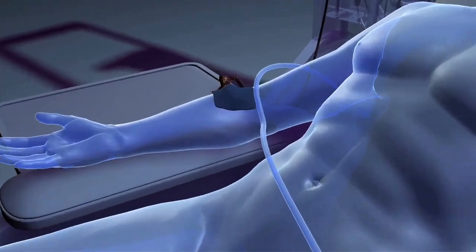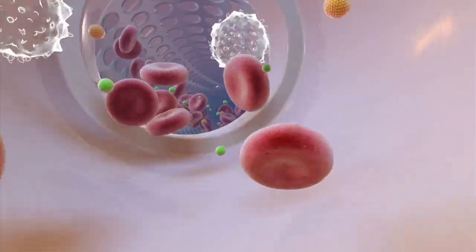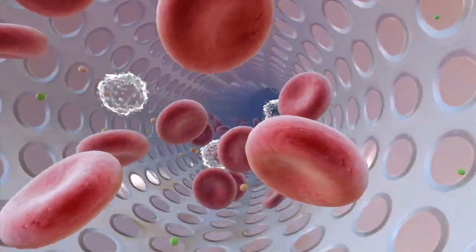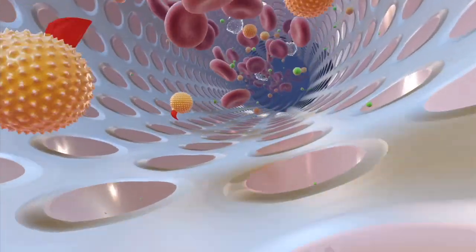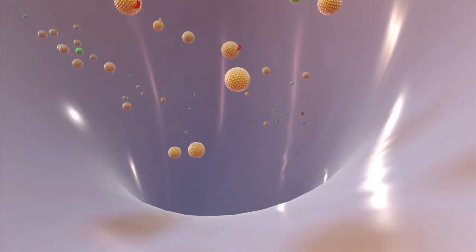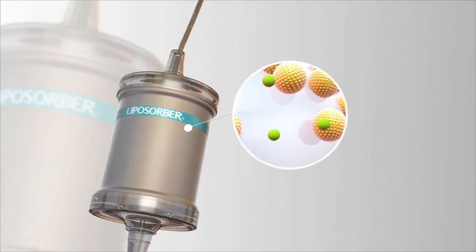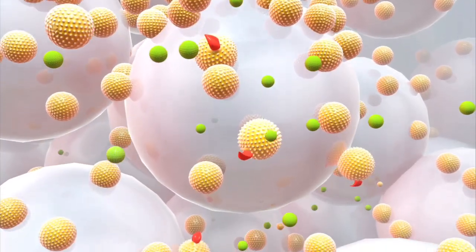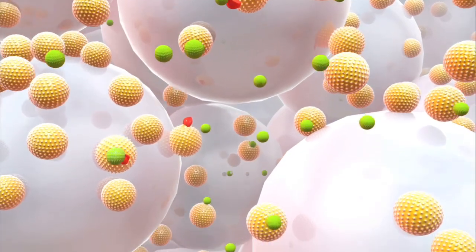Blood is withdrawn through a needle in one arm and returned in the other. The machine separates plasma from whole blood. Plasma is then routed to one of two adsorption columns that remove atherogenic lipoproteins such as LDL, VLDL, and Lp(a).